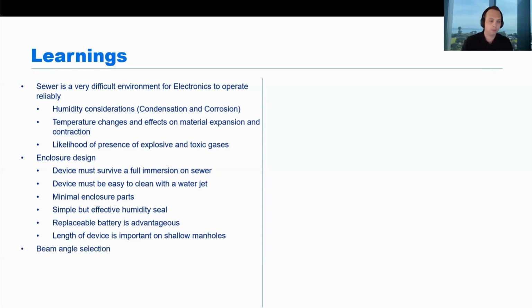The other thing is the beam angle selection that applies both for radar and ultrasonics. It's very important when you're considering narrow or deep installations because you'll have a lot of reflections if you have a wider beam angle. The other thing to consider is what protocols your devices are using. These will have a direct impact on the battery life of the device. If you have a very chatty protocol, your device will suffer and you will need a larger battery to back that up, probably having the same operational life as a device using a protocol that is less chatty.